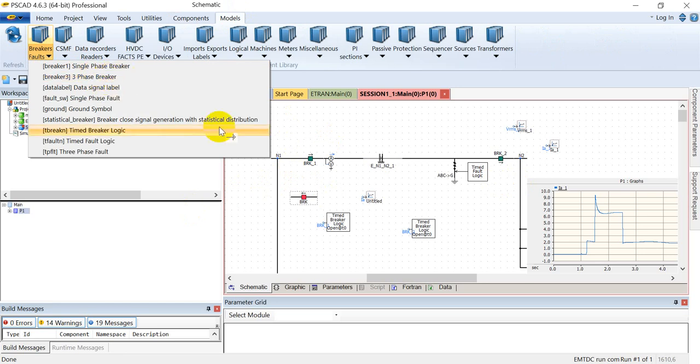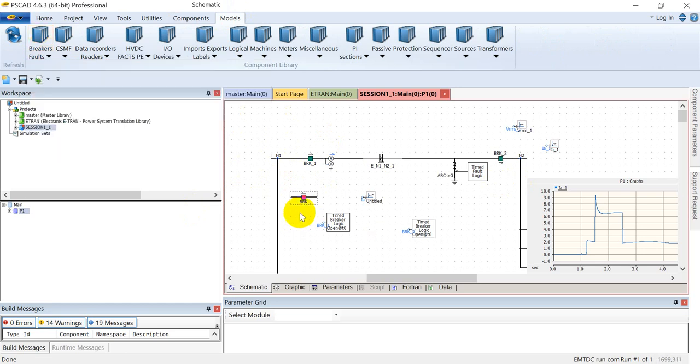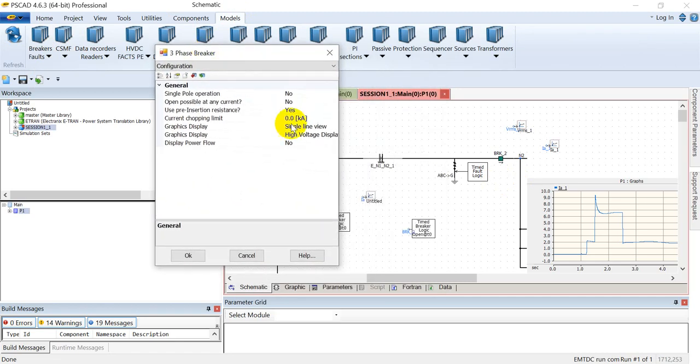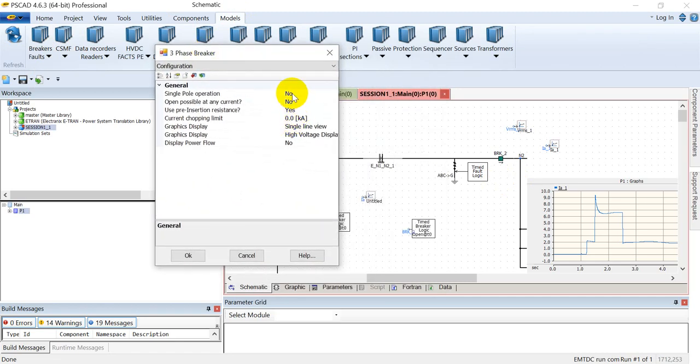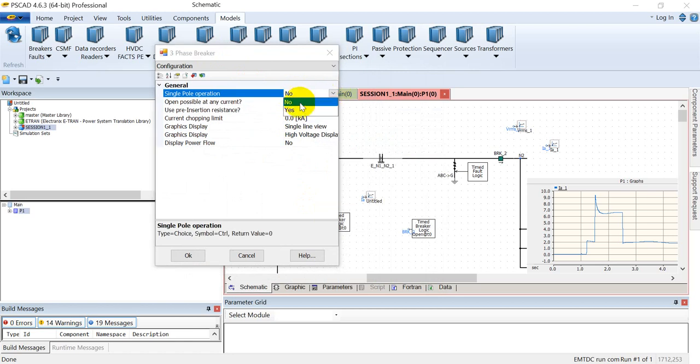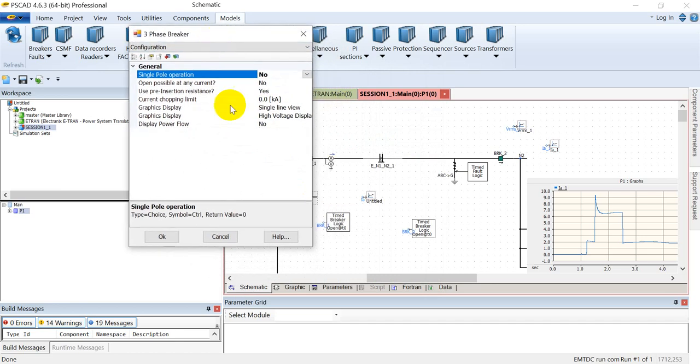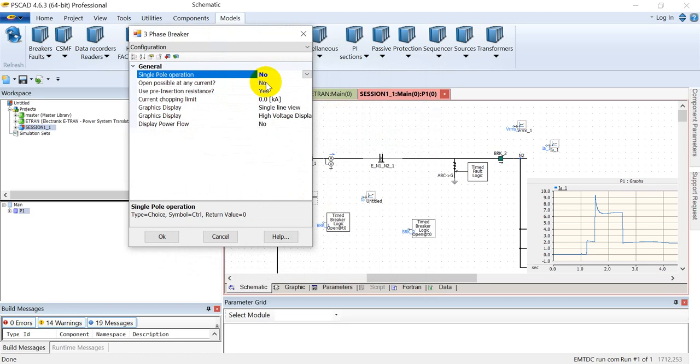Let's have a look at the various parameters of the circuit breaker. The first one is single pole operation. If we select it as yes, we can control each individual pole of the circuit breaker independently, but if we select no, then all three poles will be controlled by a single control pulse.